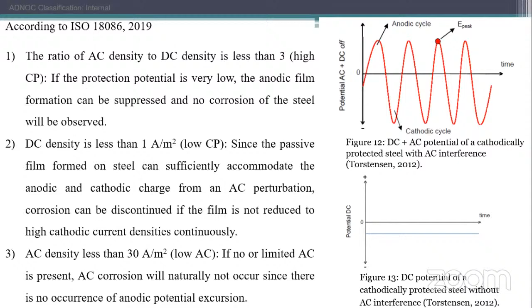Now, if the AC density is also less than 30 amps per square meter, the process will find it difficult to happen. So for AC corrosion to happen, the main center of interest is AC density. AC density is the problem. If the density of alternating current is high, corrosion will progress at that point. If it's low, it is also controlled.